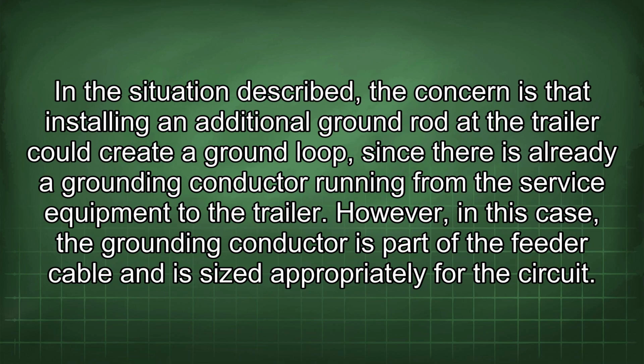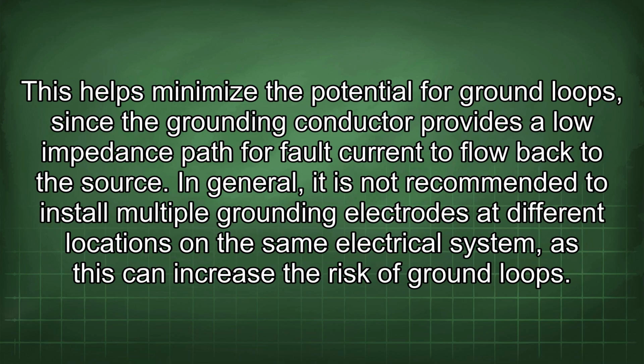In the situation described, the concern is that installing an additional ground rod at the trailer could create a ground loop, since there is already a grounding conductor running from the service equipment to the trailer. However, in this case, the grounding conductor is part of the feeder cable and is sized appropriately for the circuit. This helps minimize the potential for ground loops, since the grounding conductor provides a low impedance path for fault current to flow back to the source. In general, it is not recommended to install multiple grounding electrodes at different locations on the same electrical system, as this can increase the risk of ground loops.